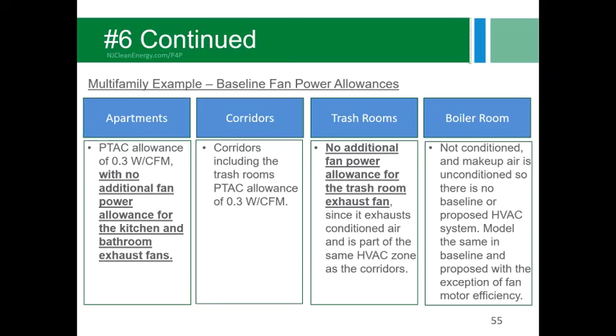And then the boiler room, it's not conditioned, and makeup air is unconditioned, so there's no baseline or proposed HVAC system. So you would model it the same in the baseline and proposed, with the exception that the fan motor efficiency would be modeled with the efficiency per Appendix G in the baseline, and then with the proposed design actual fan efficiency. So if you have a high efficiency fan, you can get a little bit of credit there.